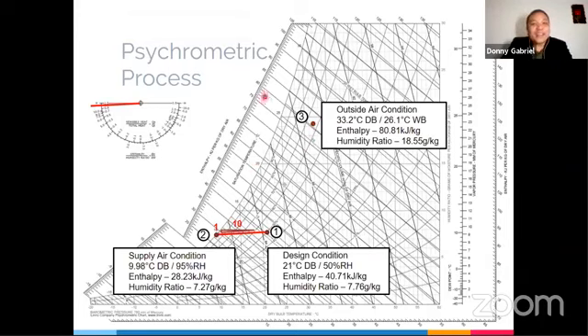So for example, here you would see 80, or your pen slightly got disoriented, you would get 81. So which means all your calculation preceding that would be different already. So for example, here I put 80.81. Of course, our eyes will not see 81. We will see 80. Instead of 80.81, our calculation will be at 80 or 81, because a psychrometric chart is a graphical process. So if you use your formulas, of course you will get a different number, but it will be a similar number. From my experience, for example, I will get 200 kilowatt, but on my formula, I will get 198 or 188. So it will be roughly the same, but not exactly the same, but it will be within the range.